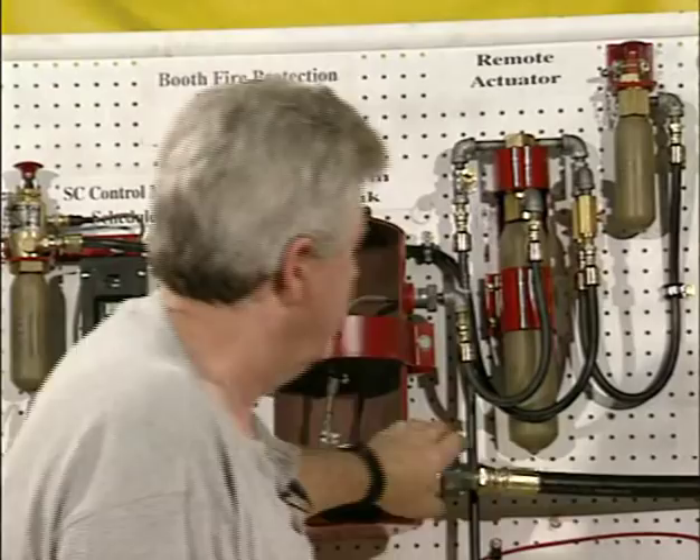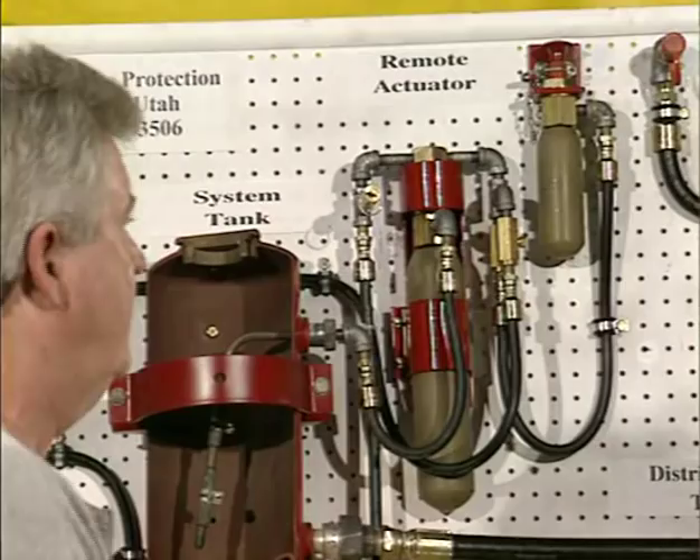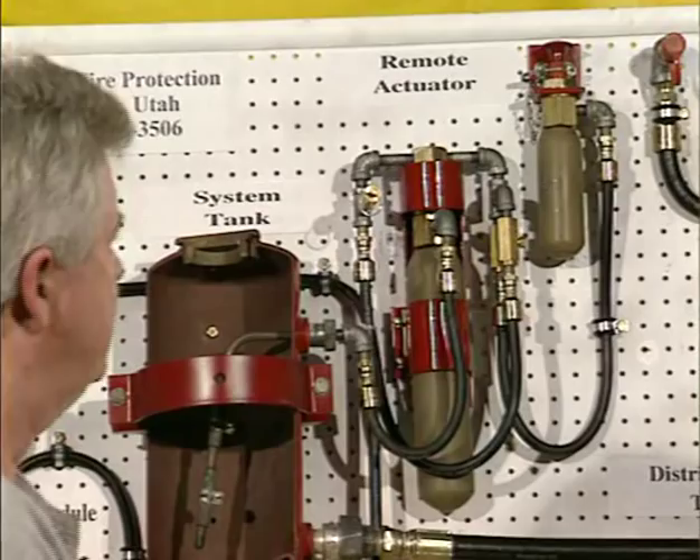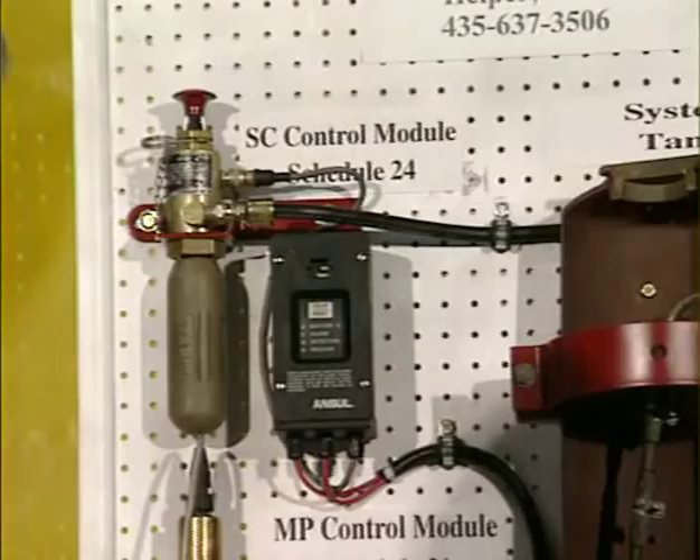The check valve splits the system so you can have up to 75 feet on each side — 75 feet is the maximum on either side because the check valves break that system up. Every check valve ANSUL sends with the system has an arrow showing the direction of flow. If a check valve is put in backwards, it will stop the system from activating.